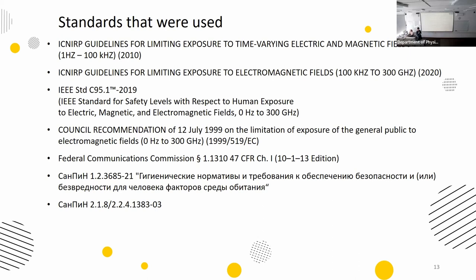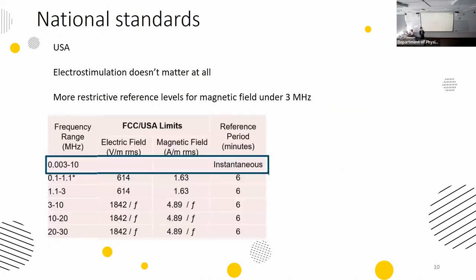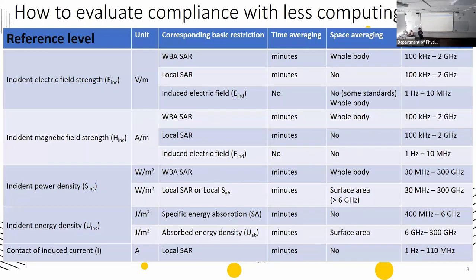A final question: for near-field scenarios, isn't it correct to say that incident power density is only applicable for far-field scenarios? In near-fields, the power density may be complex. The answer is yes — in the standard, for far-field you can calculate either incident power density, or separate electric and magnetic field strengths. For local SAR, you either calculate it for far-fields using power density, or use the two separate field quantities for near-fields.